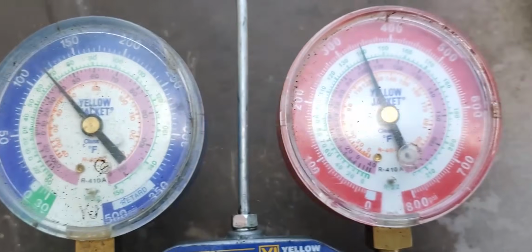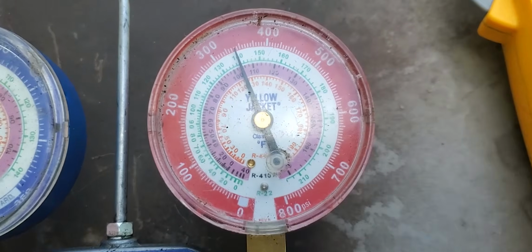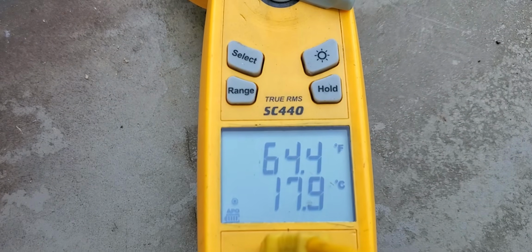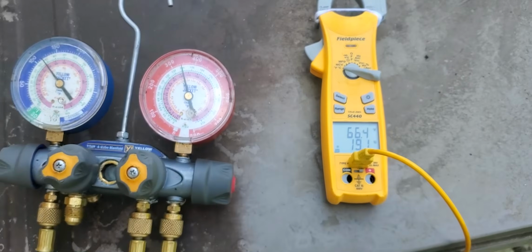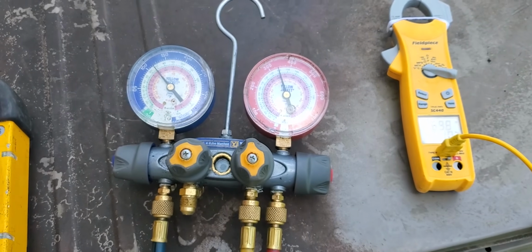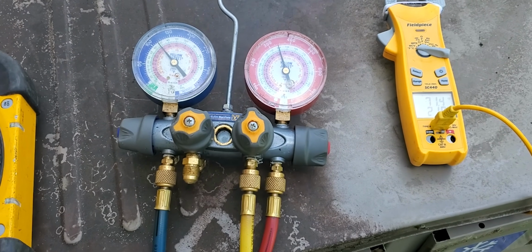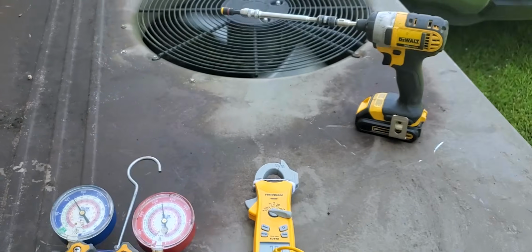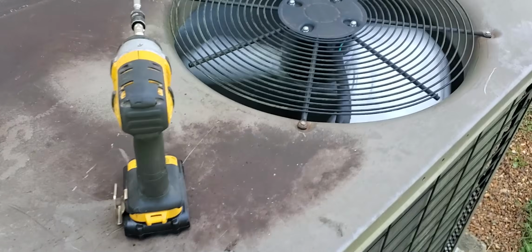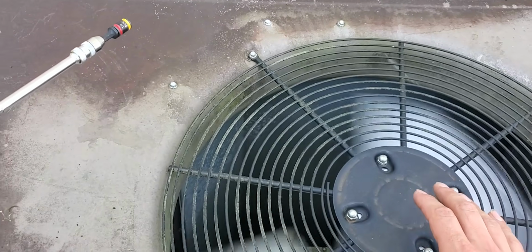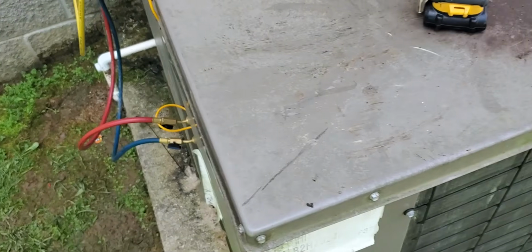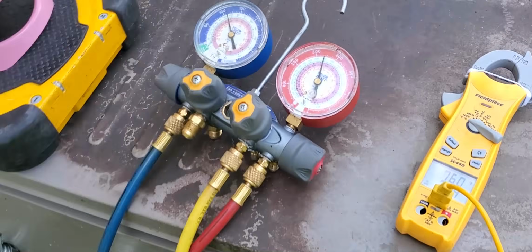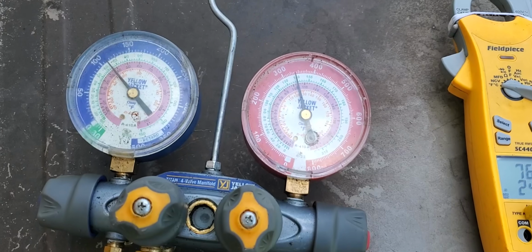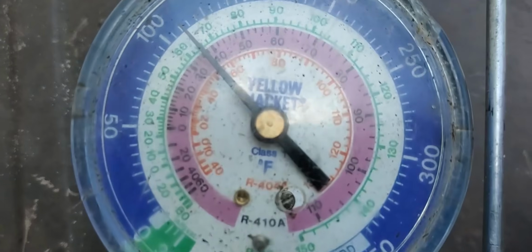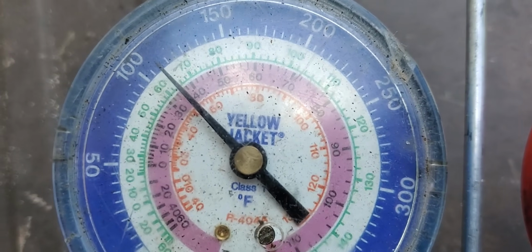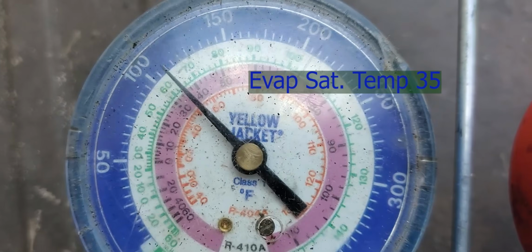You get your PSI. You use the evaporator pressure measurement to determine the saturation temperature of the refrigerant in the evaporator. There are two ways of doing this. Some gauges display the saturated refrigerant temperatures that correspond with the pressure measurement. If your gauge does not, you just get a PT chart like I talked about when we were checking subcooling, and you look and it shows the corresponding values. Record that saturation temperature.